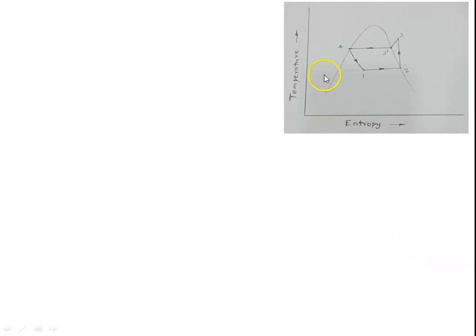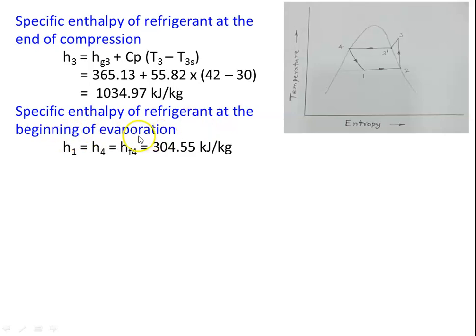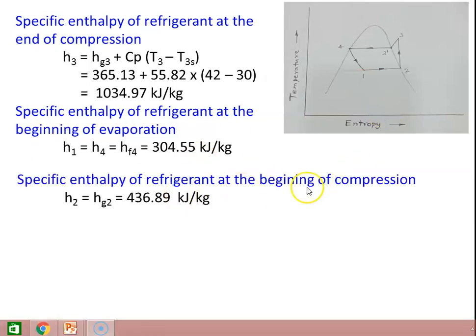The cycle and various processes are shown here. Point 2 is the saturated vapor before compression, point 4 is the saturated liquid after condensation, and point 3 is the superheated vapor after compression. The specific enthalpy at the end of compression: H3 = Hg3 + Cp × (T3 - T3s) = 365.13 + 55.82 × (42 - 30) = 1034.97 kJ/kg. H1 = H4 = Hf4 = 304.55 kJ/kg. H2 = Hg2 = 436.89 kJ/kg (saturated vapor).